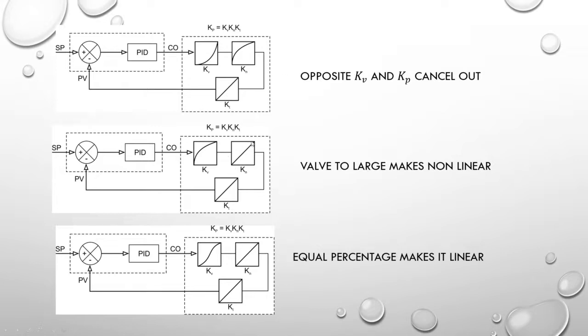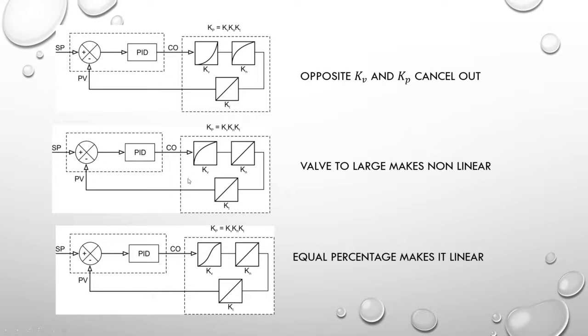If I have a relatively linear process and transmitter, a valve that's too large will give quite a lot of flow at zero to 10% opening — that's no good. To fix this, I can select an equal percentage valve to straighten out the line. This represents a valve that's too large with too much flow in the opening portion of the valve stroke. By changing a quick opening valve to an equal percentage valve, I can eliminate the non-linearities to a major degree just by selecting different valve trim.